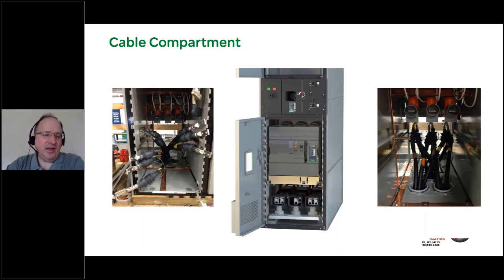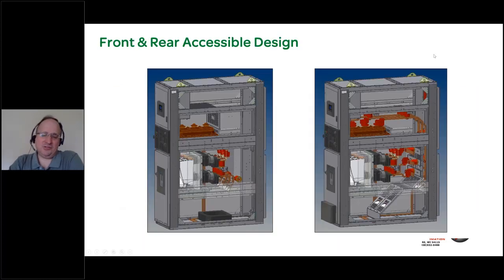But in all cases, we've installed a lot of this equipment already and haven't had any complaints from any of the electricians who've installed it. People are getting used to the fact that equipment which is smaller and more compact is a tighter fit during the installation process, but it requires so much less maintenance, is so much safer, and costs less, that those advantages are compelling. You have to take the pluses and the minuses whenever you go to a compact design with respect to installation difficulty. And as previously noted, we have both front and rear accessible designs in this equipment.